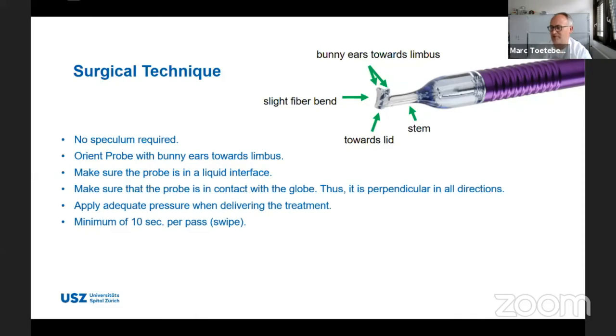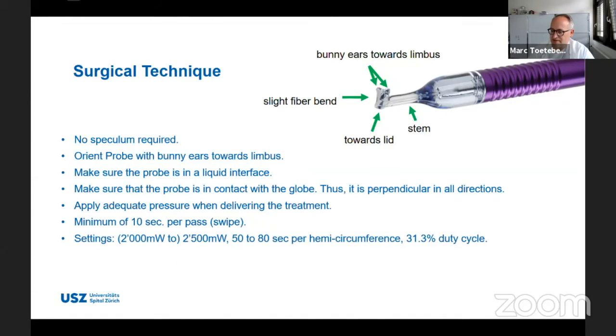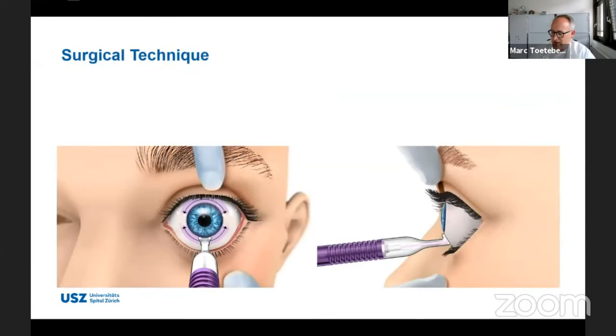And there's a little bit of variation and discussion about how fast, or better, how slow you should swipe doing your passes. I recommend at least 10 seconds. Do it slower if you want to have better results. That's what we get at the moment, 15 seconds or better, even 20 seconds per swipe. And the settings can also vary between 2000 milliwatt and 2500 milliwatt, 50 to 80 seconds per hemicircumference, and the duty cycle is set to 31% with the machine in general.